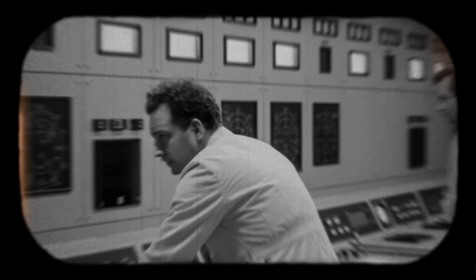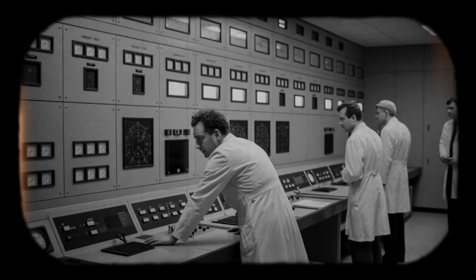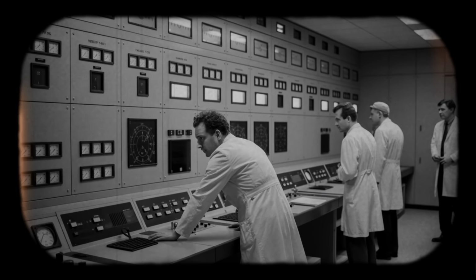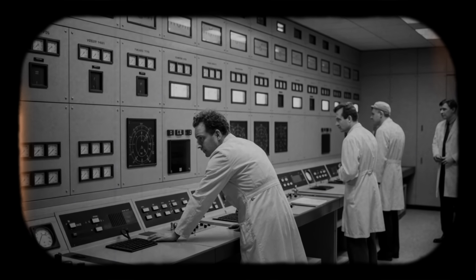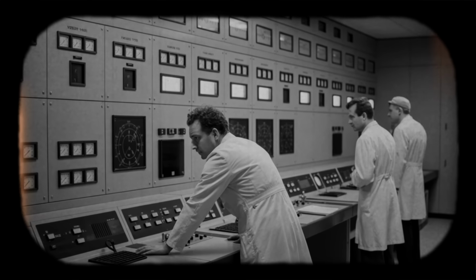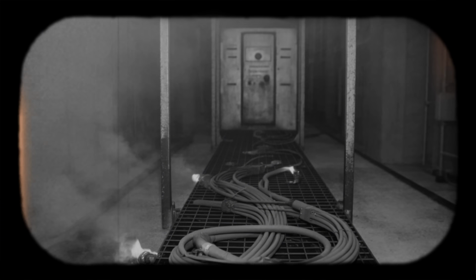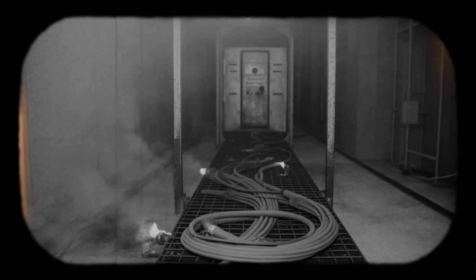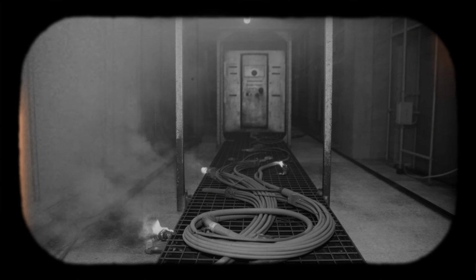7th of December 1975, Greifswald Nuclear Power Plant, Lübmin, East Germany. Unit 1 runs at full power, 6 loops circulating coolant through a Soviet-designed VVER 440 reactor. At 11:08, a control room alarm announces a fault in the 6 kV standby switchgear, an electrical system formerly not required for reactor operation. An electrician's switching error produces a high short-circuit current. An automatic breaker fails to clear it.